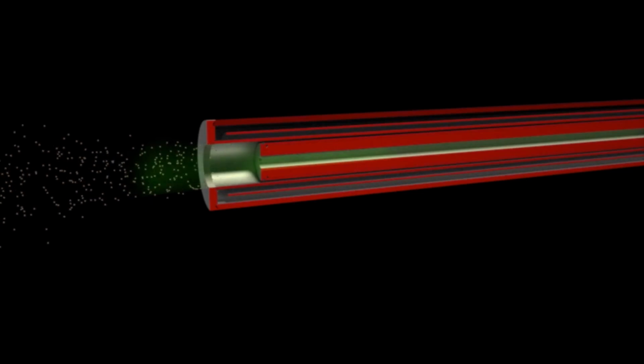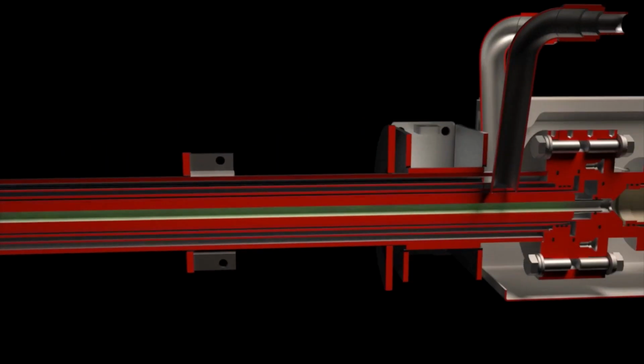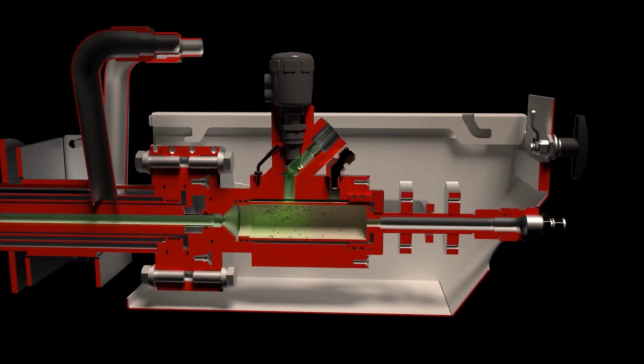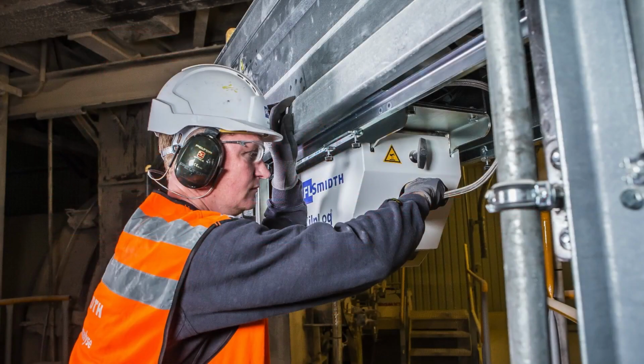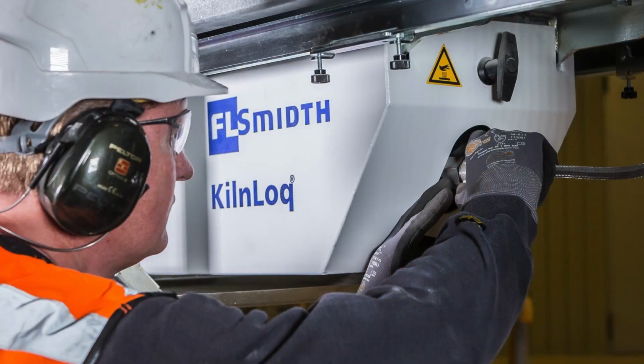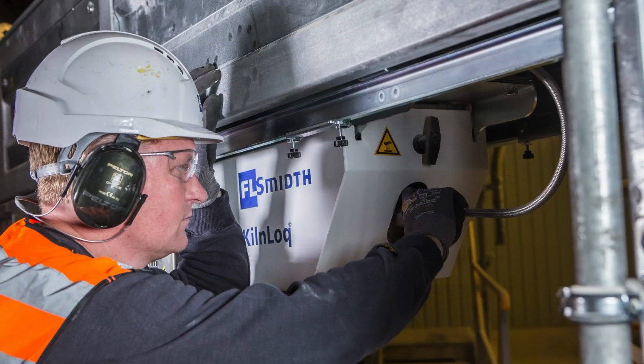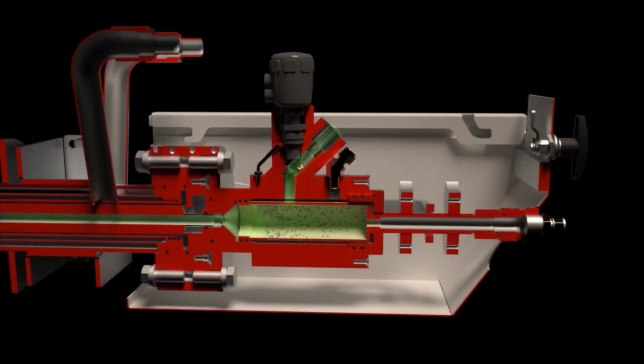The one-pipe probe is water-cooled and provides trouble-free operation in the highly corrosive, dust-filled kiln environment. It samples gas in a straight line with no bends, obstacles or deposits to interfere with the sample collection. The process gas enters the filter housing through the centre of the pipe, where it passes through a built-in filter for collection and analysis. By opening the access port at the end of the KilnLoq, operators can undertake a real-time visual inspection of the probe and kiln processes.